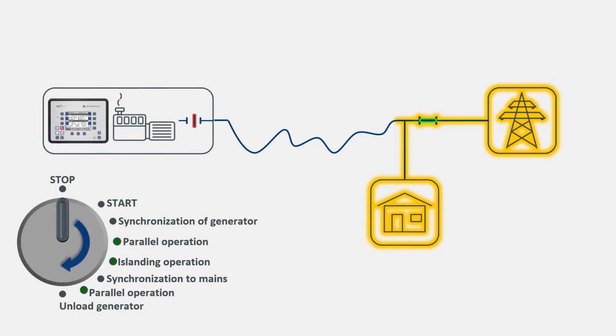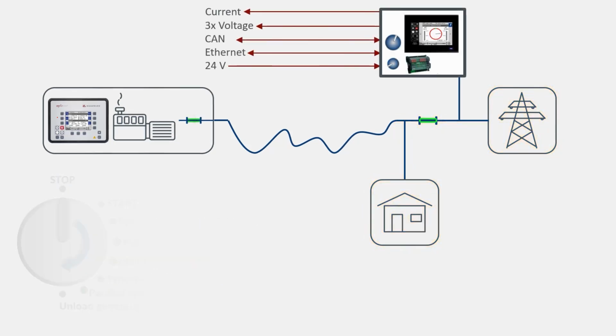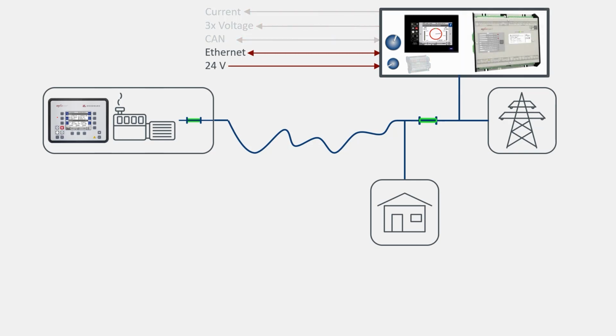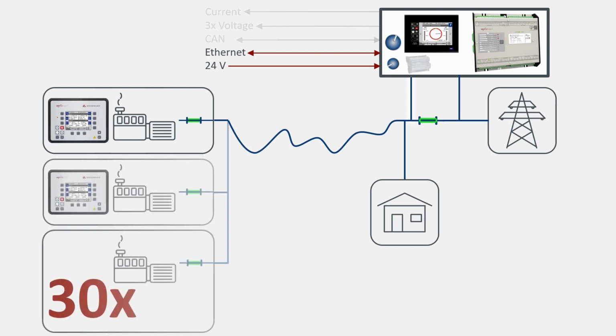For single generator applications with larger distances between the generator and the mains breaker, and especially for generator fleet applications, consider using an LS6 XT mains breaker controller. This comes with current sensing to measure power at the incoming mains feeder. While this will require an additional measurement at the mains breaker, it will slim down the cable tree to a simple Ethernet cable and a 24 volts power supply.